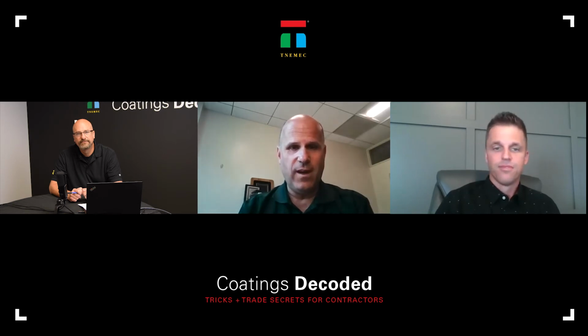Okay. And so Peter, you talk about this R-value equivalency when the sun's out, so I guess that would be impacted too if the surface was dirty. Certainly a material could perform a certain way when it's applied new, because it might require a certain color, certain level of cleanliness and condition, even a certain surface roughness associated with it. And then if it gets covered in pollen or whatever might be around there, suddenly it's not going to behave in the same way as the performance you had at the beginning. Where when you're talking intrinsic material properties like thermal conductivity, if that coating got covered in dirt or pollen or whatever it might be, it will have no impact on its performance.